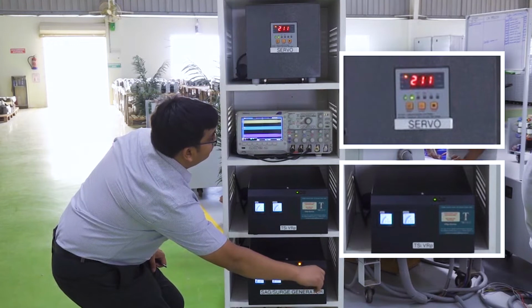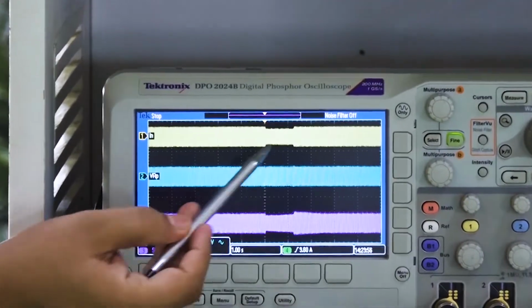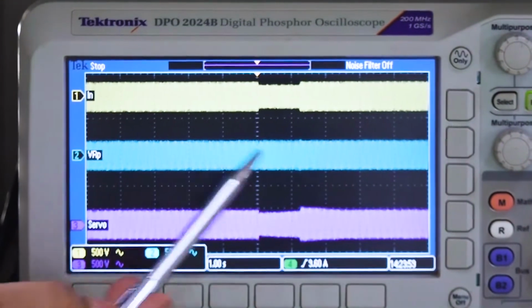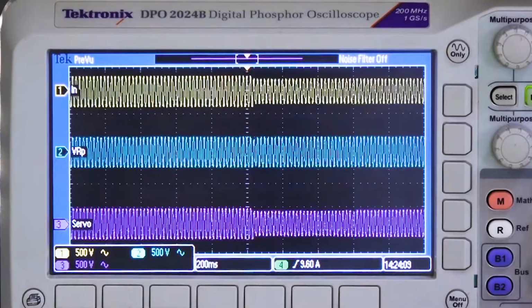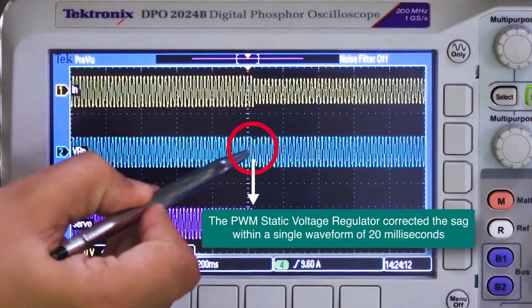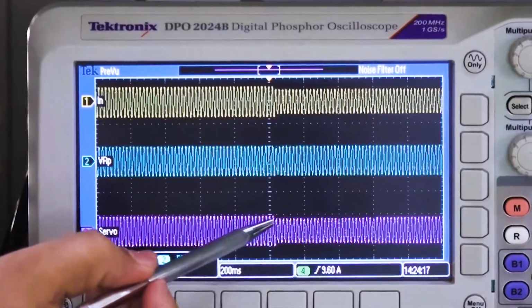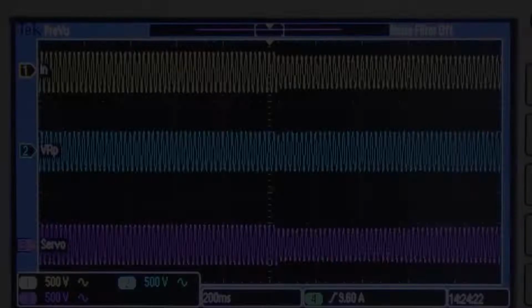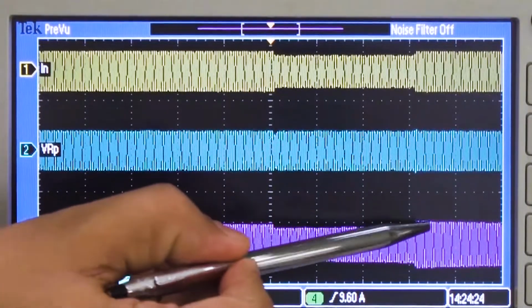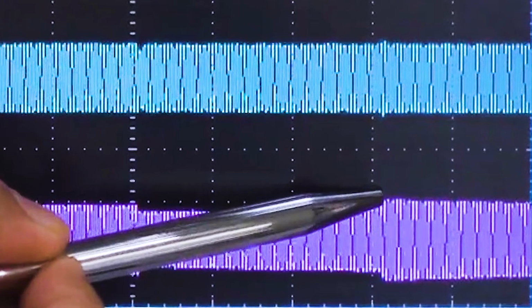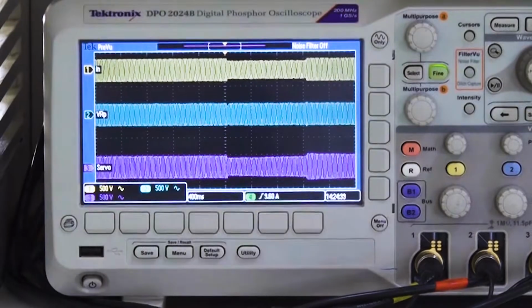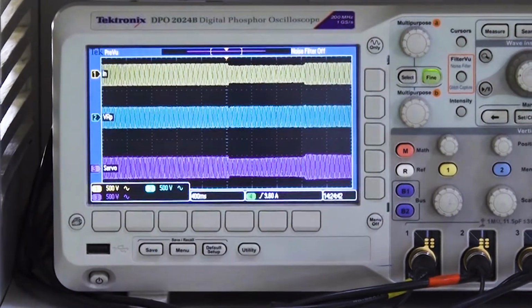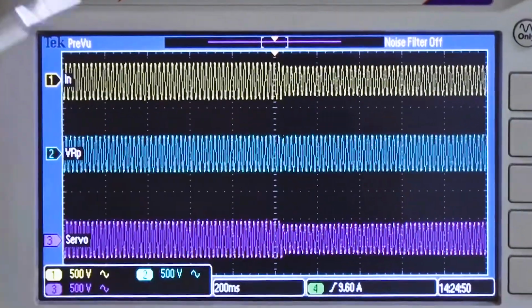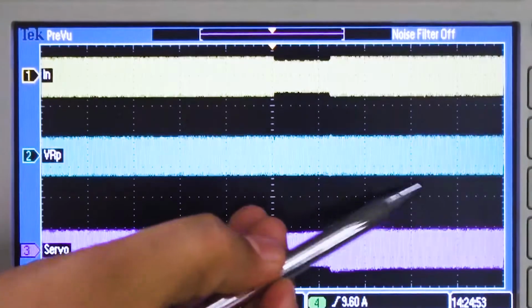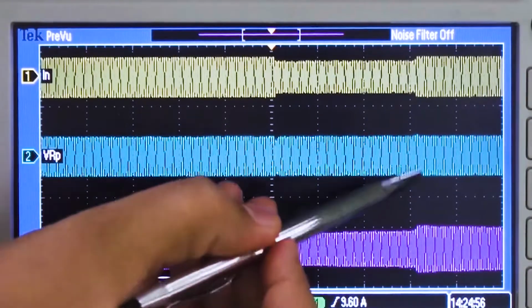We are now ready to observe a sag phenomenon. So, let's generate a short sag. As you can clearly see, a sag occurred on the input side of both the equipment, and both the equipment behaved very differently. The static voltage regulator corrected the sag within a single waveform of 20 milliseconds. But the servo voltage stabilizer took a very long time to correct. Furthermore, in the case of servo voltage stabilizer, as soon as the sag disappeared, servo stabilizer gave a high voltage output because it was still in its boost mode. If this output high voltage was beyond the cutoff limit, then servo voltage stabilizer would trip. But nothing of this sort happened in the case of static voltage regulator. You will observe from its waveform that it corrected everything within one waveform or within 20 milliseconds.